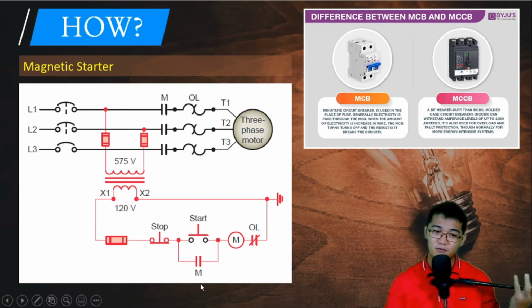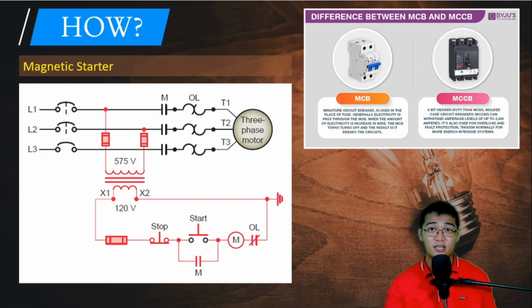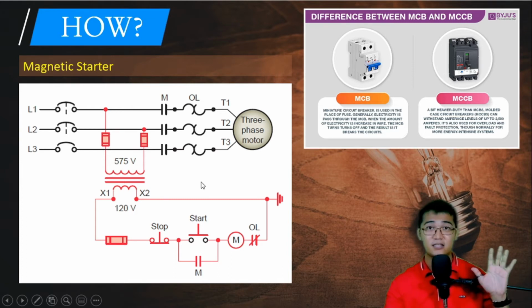And then we have this contact here. In the previous video, we discussed that whenever we connect an auxiliary contact, normally open, of a contactor in parallel with a push button switch, this functions as a holding contact. Meaning, when we press it, since the push button is momentary, once we release it goes back to normally open, so this particular contact provides another path.